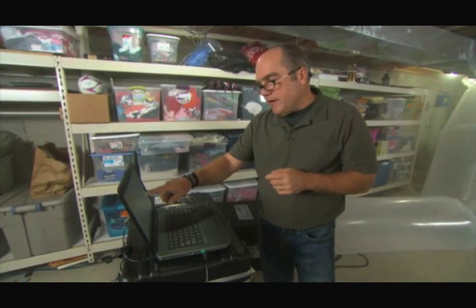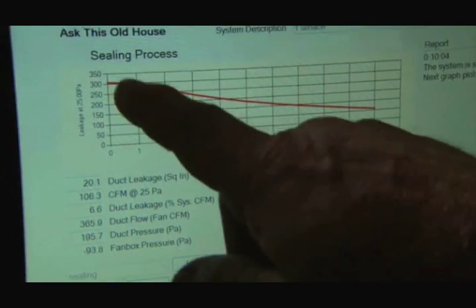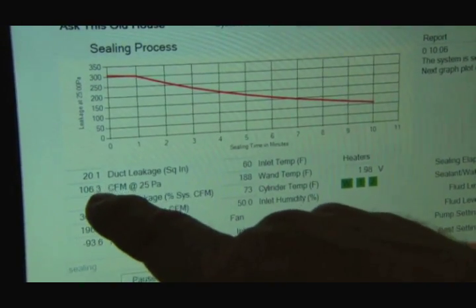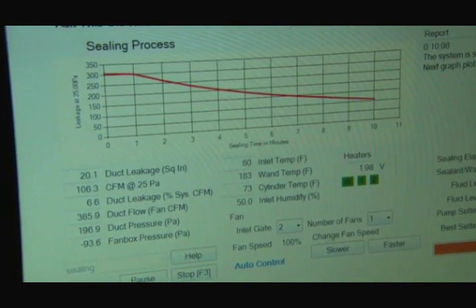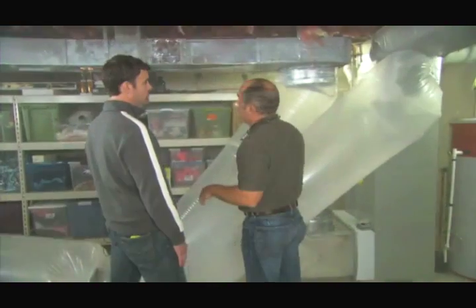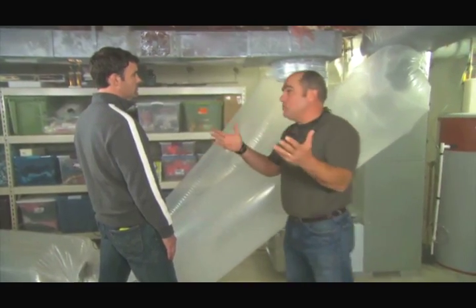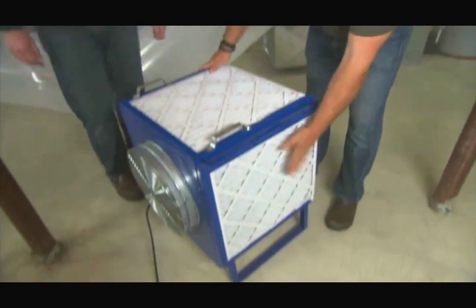seal any duct leakage. All right, so we've been running for about 10 minutes, and we've gone from 300 CFM of leakage down to 100 already, and we're not done yet. Pretty cool. Now, any of the sealant that happens to leak into the living space can be captured from this scrubber fan onto the filters.